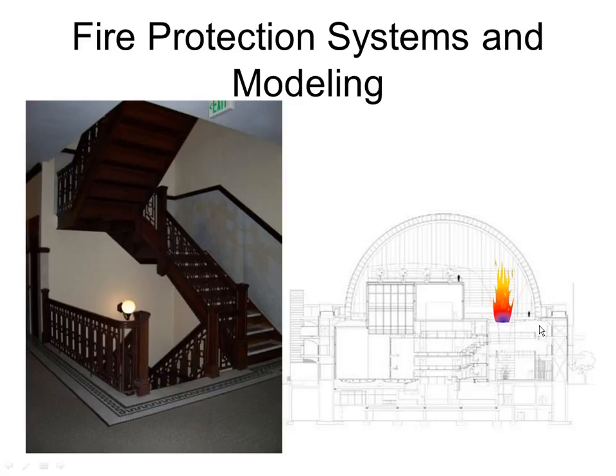We can create a computer model that takes into consideration the geometry of the space and identify fire growth and determine if the space can be maintained in a tenable condition until occupants are safe. Either they evacuate or they're able to defend in place. And for the TUI building, we were able to demonstrate that with the addition of a sprinkler system throughout and the installation of a smoke detection system for early warning, we were able to maintain that tenable environment for the occupants of the building. And that allowed us to make that presentation to the authority having jurisdiction and allowed this beautiful stairway to remain open. So I wanted to tie in how these pieces work together.